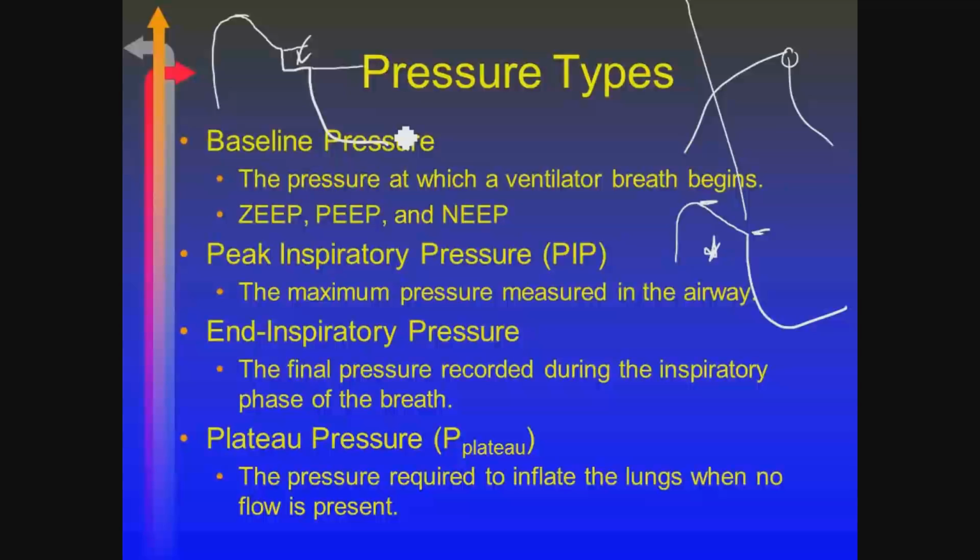So not all breaths are going to have one. Oh, no. In fact, in most cases, we don't have a static pressure, we don't have a plateau being displayed. What is the definition of a plateau? It's a period of time where I'm not allowing gas to flow. That pause that is there, zero flow, allows that equilibration to happen and the different pressure to be displayed.